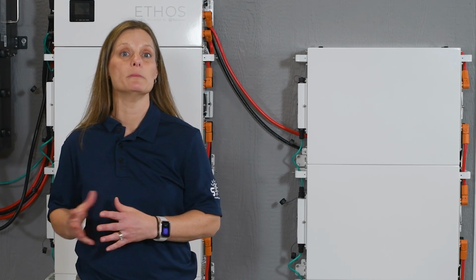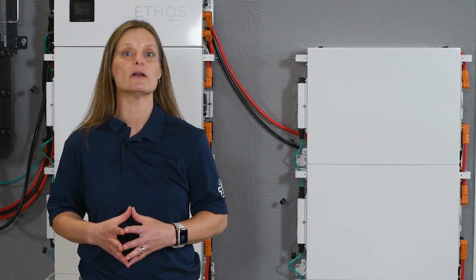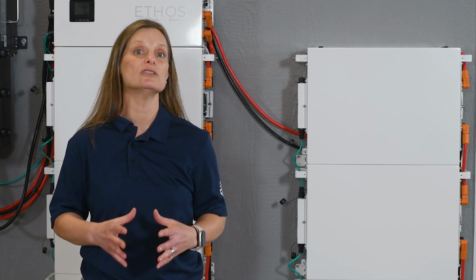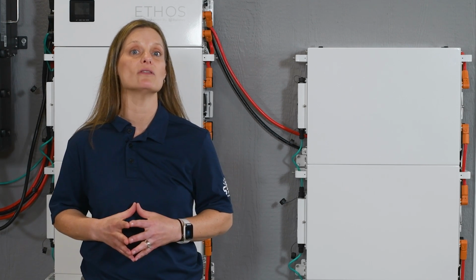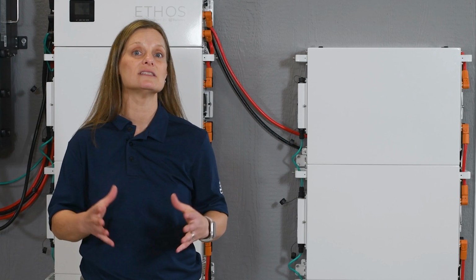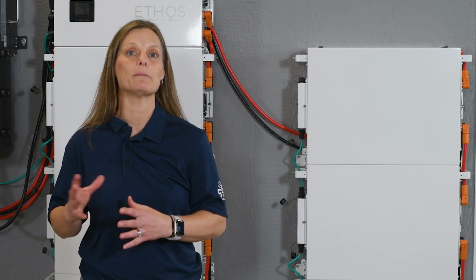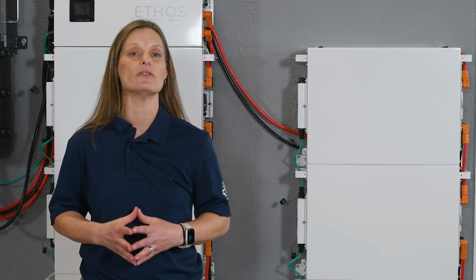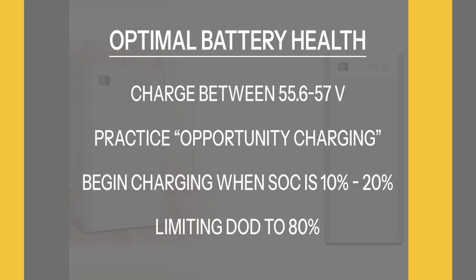As you progress with commissioning your system and integrating your batteries with the chosen inverter, it's essential to consider several guidelines outlined in the manual. These are designed to ensure your batteries operate at peak efficiency and maintain their health over time. Here are some key tips to remember. Adhere strictly to the charge settings specified in the manual. The recommended voltage range for charging is between 55.6 to 57 volts.